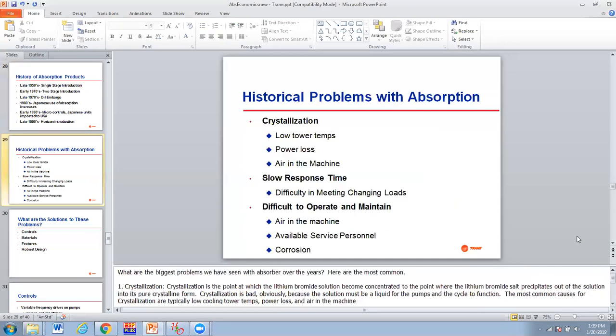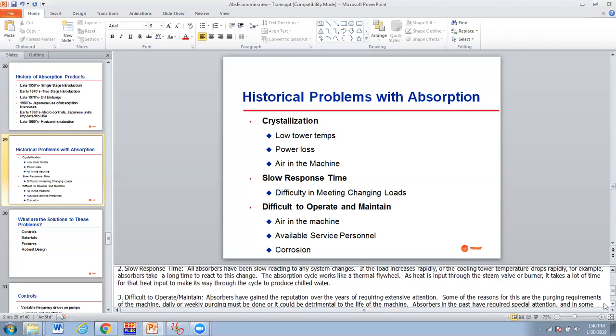Okay, so these are the problems. We've been through crystallization, power loss, and air in the machine. So those are the causes of crystallization, so we don't have to go back through those. Slow response, we'll hit that and talk about it a little bit more here. All absorbers have traditionally been slow reacting to any changes in system load. If load increases rapidly or cooling tower temperature drops, those are examples that can take the absorption chiller a long time to react properly. The absorption cycle works like a thermal flywheel.